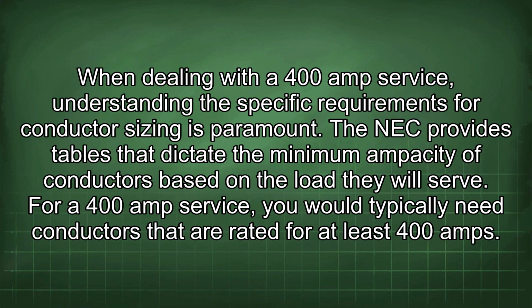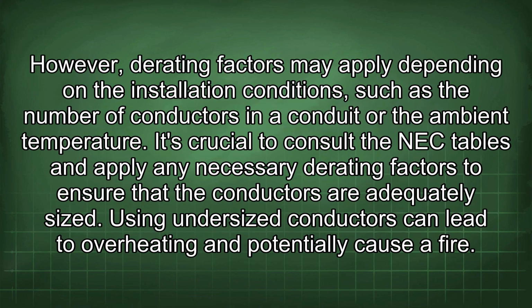When dealing with a 400 amp service, understanding the specific requirements for conductor sizing is paramount. The NEC provides tables that dictate the minimum ampacity of conductors based on the load they will serve. For a 400 amp service, you would typically need conductors that are rated for at least 400 amps. However, derating factors may apply depending on the installation conditions, such as the number of conductors in a conduit or the ambient temperature. It's crucial to consult the NEC tables and apply any necessary derating factors to ensure that the conductors are adequately sized. Using undersized conductors can lead to overheating and potentially cause a fire.